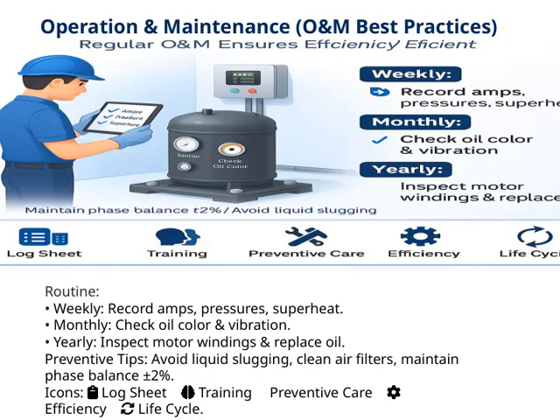Now, let's talk about operation and maintenance best practices. First, on a weekly basis, it's crucial to record key parameters like amps, pressures, and superheat. These measurements help us monitor system performance and catch any irregularities early. Then, every month, we should check the oil color and vibration levels. These are good indicators of equipment health. And once a year, it's important to inspect the motor windings and replace the oil if needed, to keep everything running smoothly.